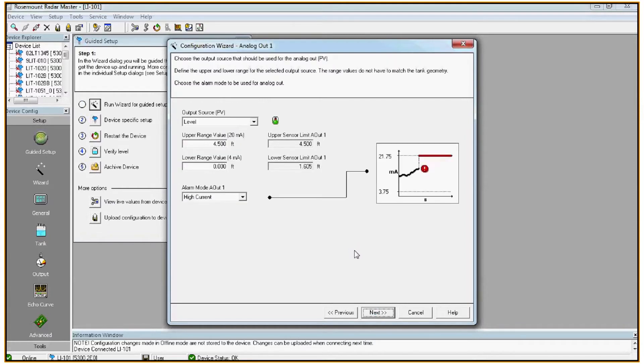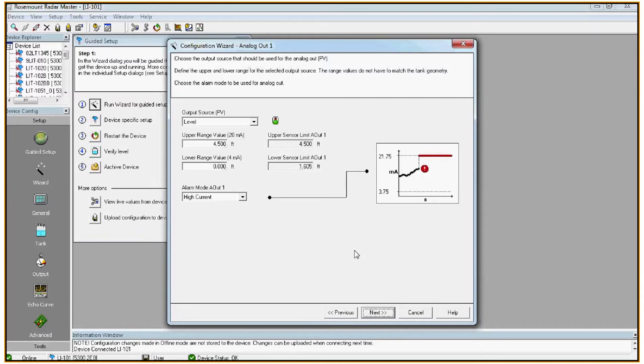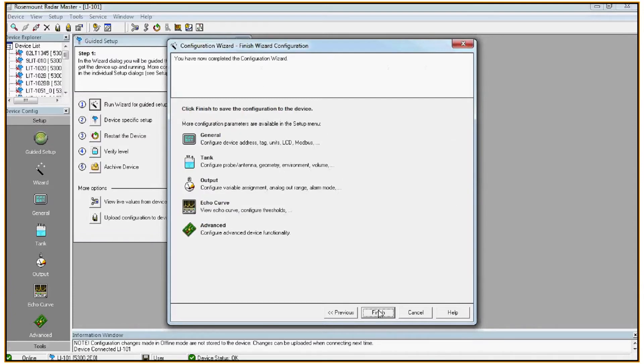And lastly you need to configure the analog output range. So in this case we've got a total tank height of five feet including a half a foot nozzle off the top of the tank. So logically it would make sense to have the analog output scaled for the bottom of the tank to the top of the tank before it enters the nozzle. So in that case I chose 4.5 feet as my 100% upper range value. Click finish.